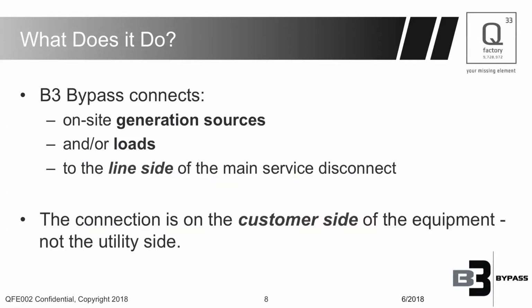It allows us to connect on-site generation sources or loads, such as EV chargers, a spa, or an HVAC system, that typically would require a main panel upgrade, and it connects them to the line side of the main service, not the load side. This is customer-owned equipment. The utility has no jurisdiction over this. That's part of the fear that many installers have: can we do this? Will the utility allow us to do it? It's customer-owned equipment, the main panel. We're installing this between the meter and the main breaker, and so there is no limitation from the utility on how we can do this.